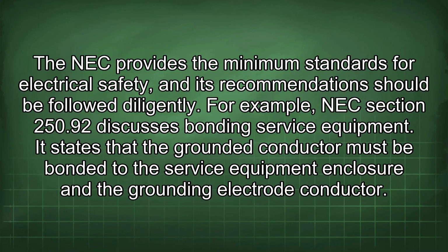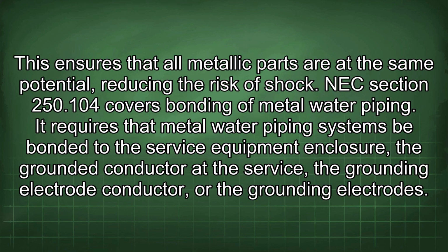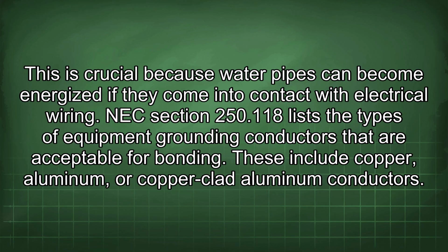For example, NEC Section 250.92 discusses bonding service equipment. It states that the grounded conductor must be bonded to the service equipment enclosure and the grounding electrode conductor. This ensures that all metallic parts are at the same potential, reducing the risk of shock. NEC Section 250.104 covers bonding of metal water piping. It requires that metal water piping systems be bonded to the service equipment enclosure, the grounded conductor at the service, the grounding electrode conductor, or the grounding electrodes. This is crucial because water pipes can become energized if they come into contact with electrical wiring.